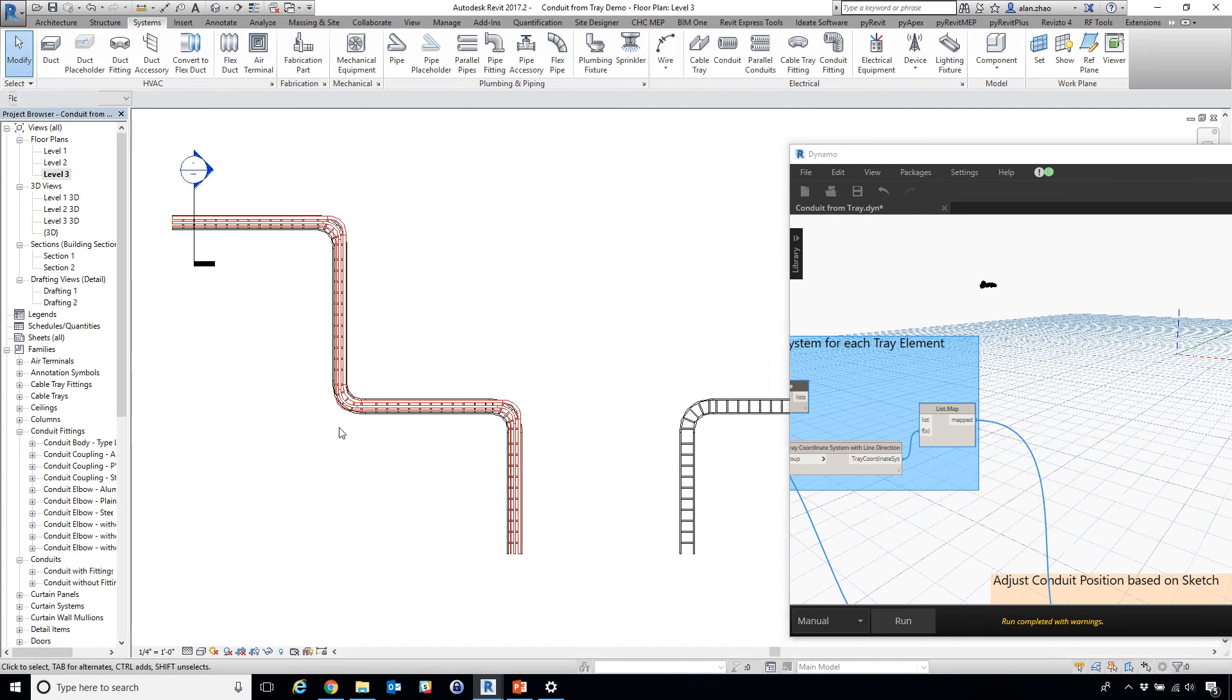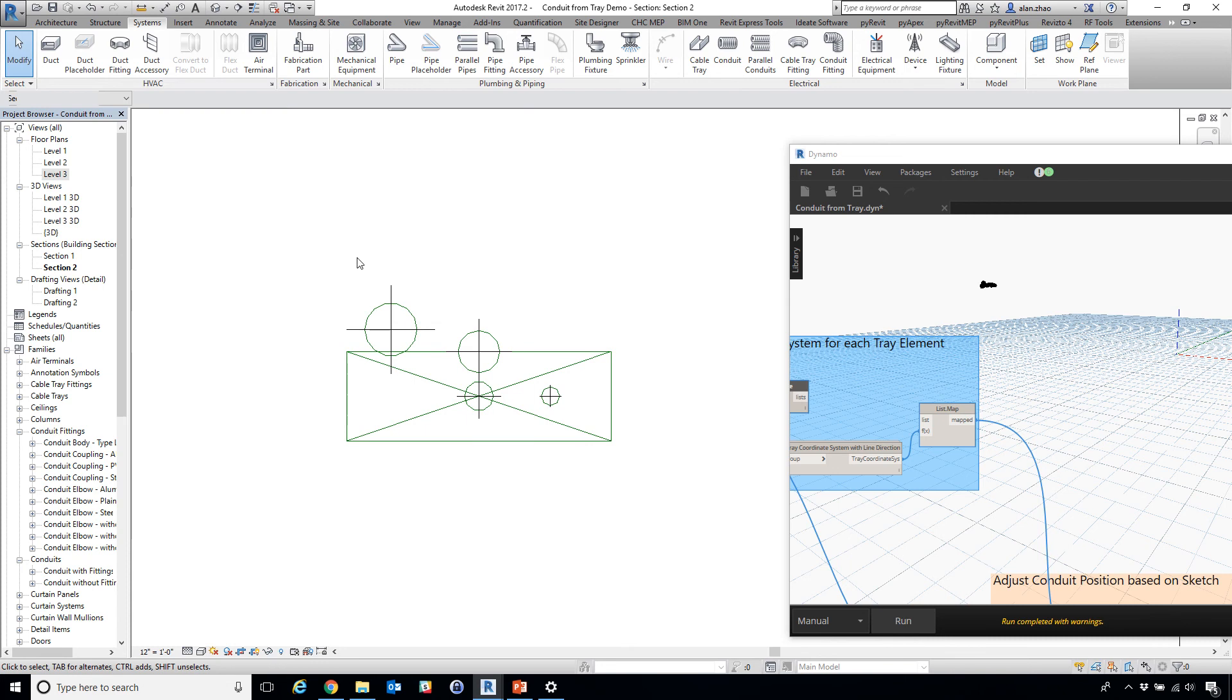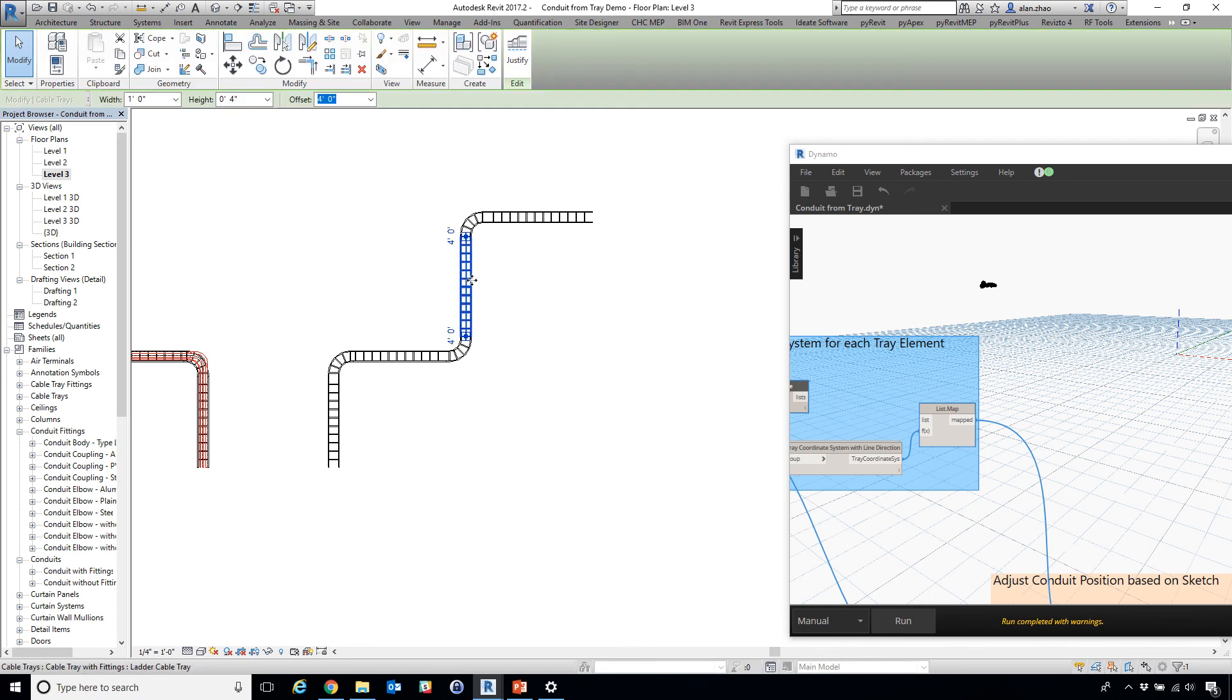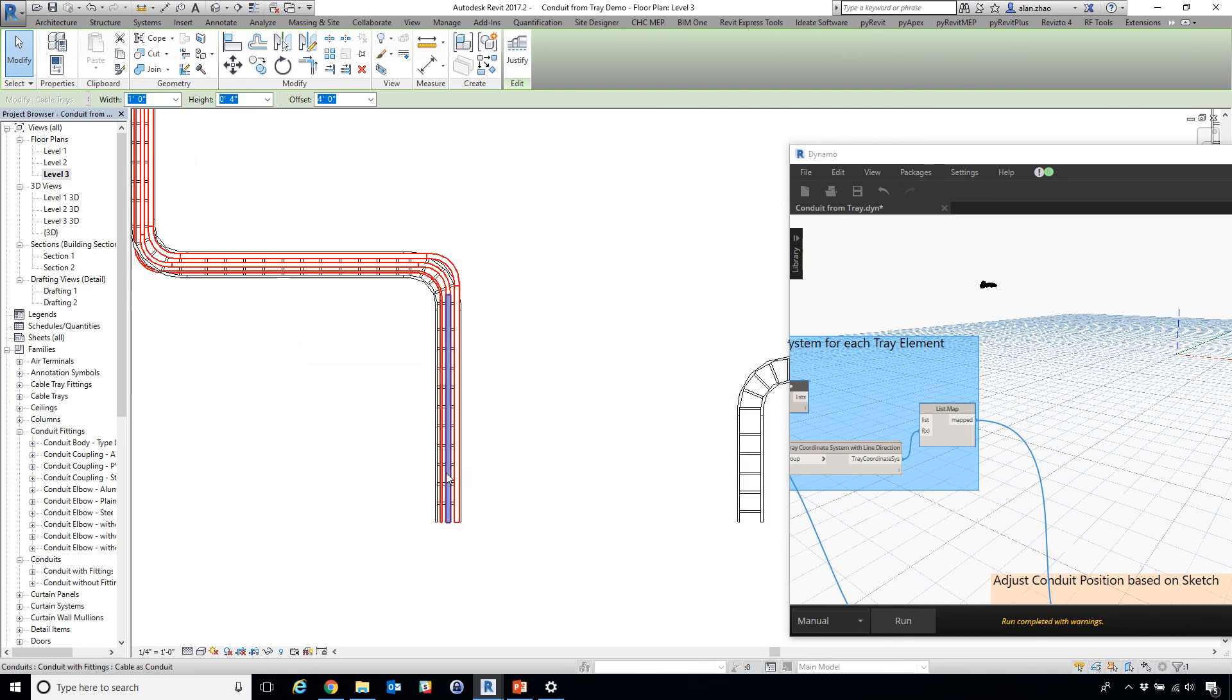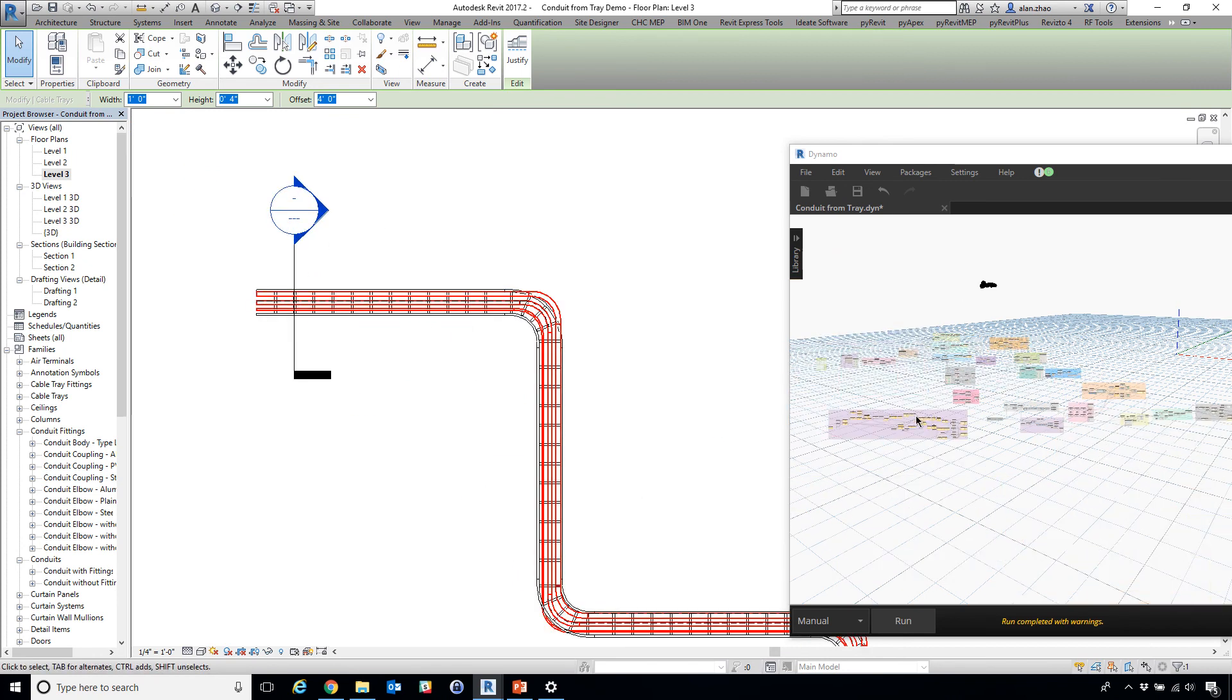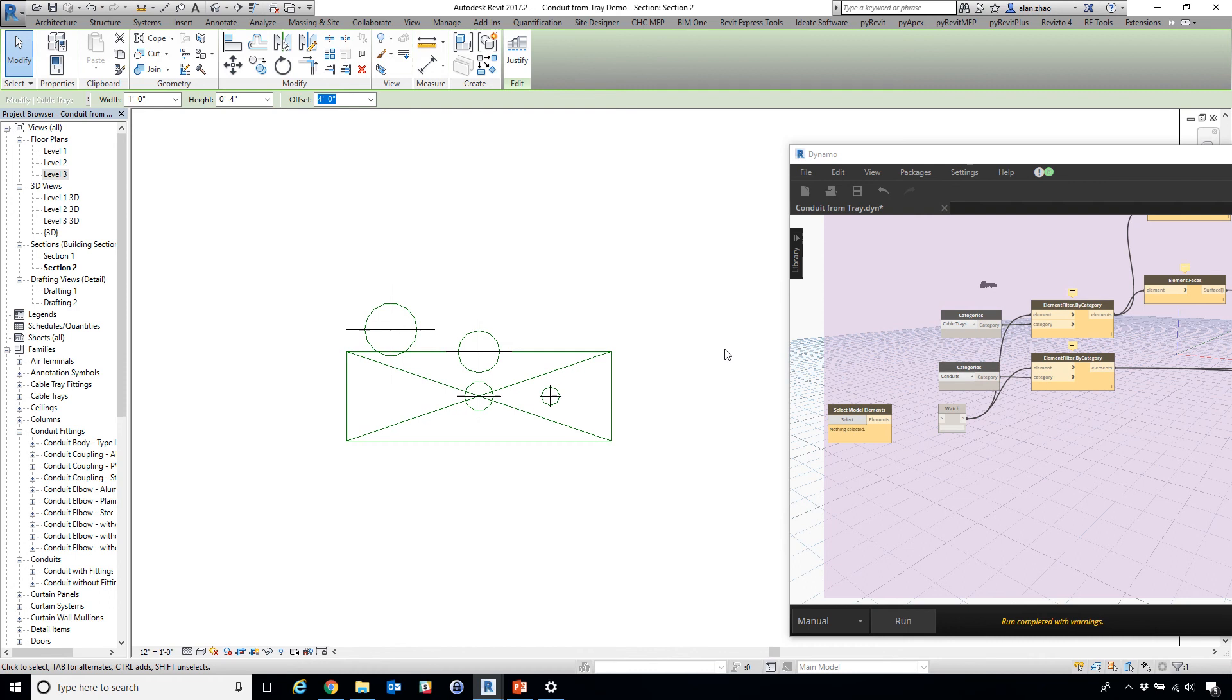In another case we have some pre-established elements. For example, we model some existing cables along existing tray, we have existing cross sections, and we want to basically make the same thing happening on the other side. Well in this case we can just use the mirror, but if we have a different layout it's going to be more difficult to make the same cross sections. So there's another piece of code here. This piece of code will take this cross sections and generate a drafting view so that we can use that drafting view to do the same conduit layout on the other tray network.